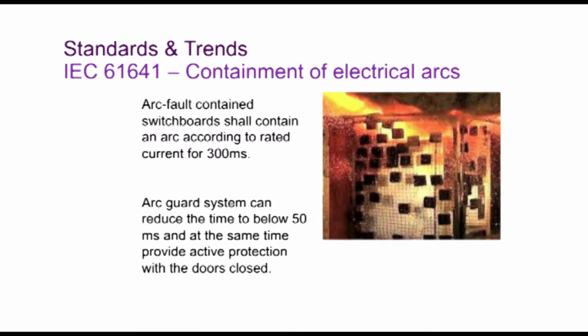Based on IEC 61641, electric arc fault containment, it states that arc fault contained switchboards generally have to contain the arc fault for up to about 300 milliseconds, because they expect your short circuit protection relay to kick in by then. Now, with the arc guard system, we can reduce that tripping time to about 30 to 45 milliseconds.